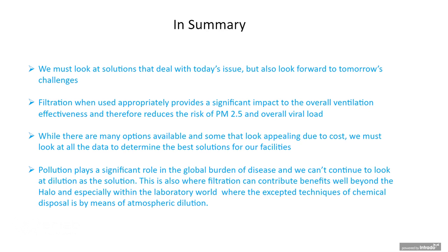Then if the ventilation system is old or it cannot be upgraded easily without significant cost. Now, the cost to upgrade a whole system, if you were adding new air handling units, increasing air changes, upgrading a system to handle a MERV 13 filter, and you don't already have something in place, we're talking millions and millions of dollars. So if the ventilation system isn't going to work for you, then you look at a whole room system that can be a combination of HEPA filtered solutions, as CDC and ASHRAE have recommended, as a supplement. That's going to provide you the proper ventilation or increased ventilation effectiveness or air change rates.